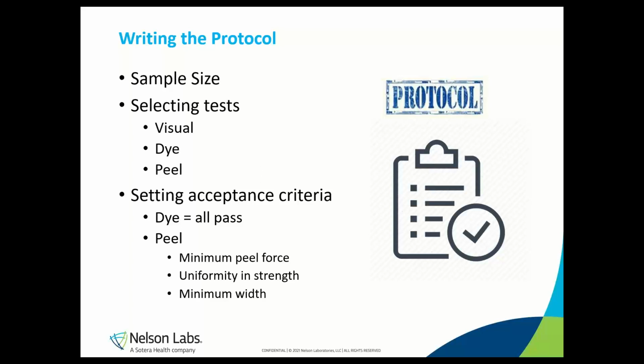If you have a visual inspection element in your validation, you need to list the expected defects and clearly define them. It is best to keep the defect list short and specific and only include defects that are relevant. Visual inspection is a good tool to make sure seals look good before committing to dye testing, and it can be very valuable if you're sending the samples to an outside lab and you want to make sure that the samples you're sending are going to be good samples.